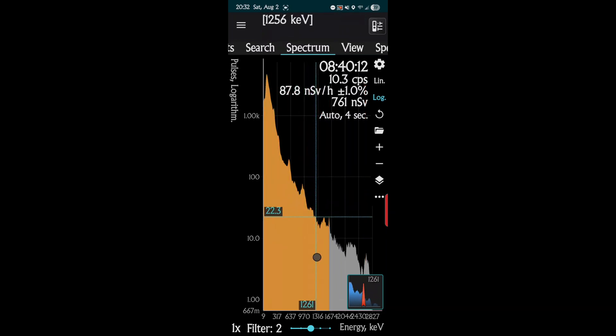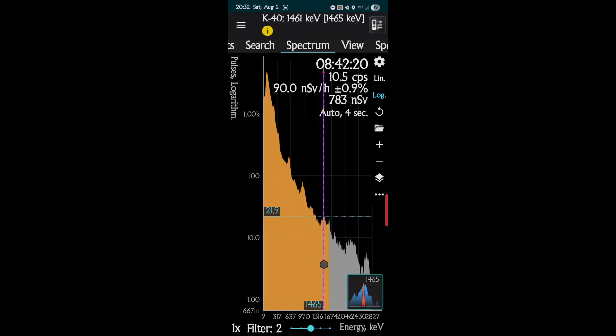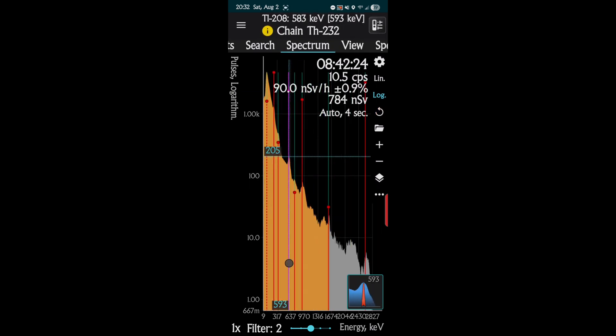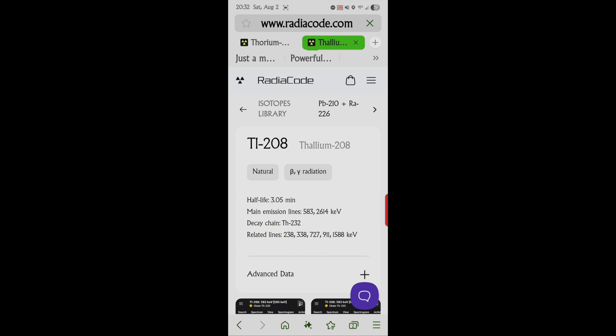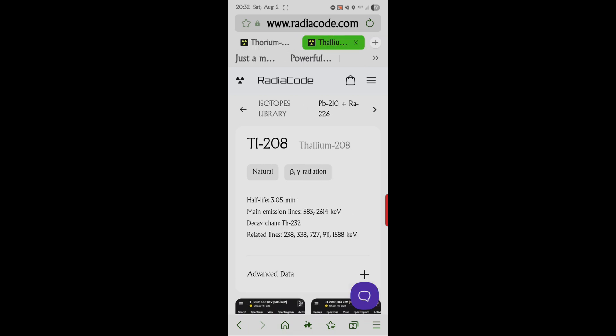Currently it's not really red yet. Looking at this peak here, it's saying that's thallium, and I need thorium. Thorium is 232, thallium is 208, so it's getting close. I've only had it on there for 8 minutes and 42 seconds, so it's getting very close to identifying correctly.